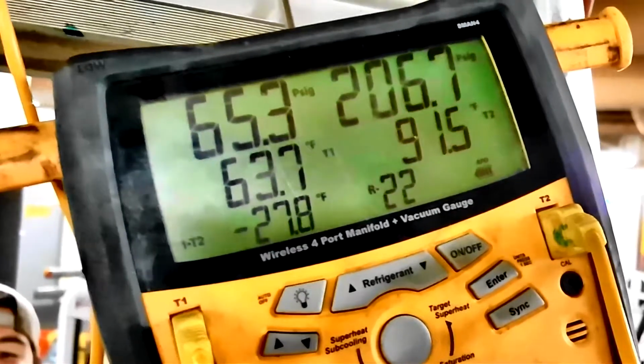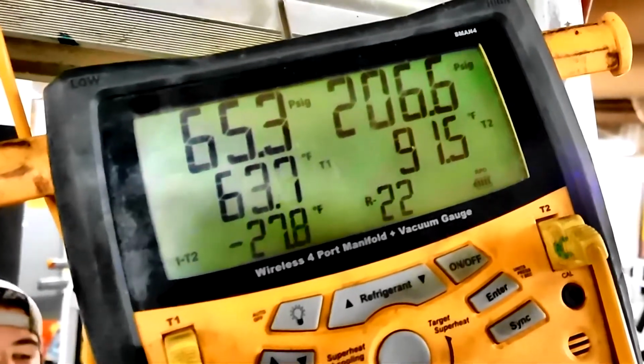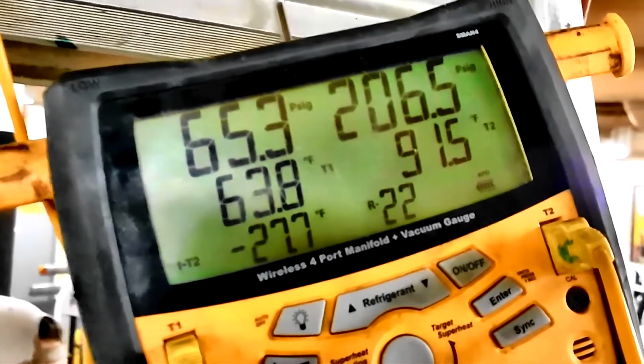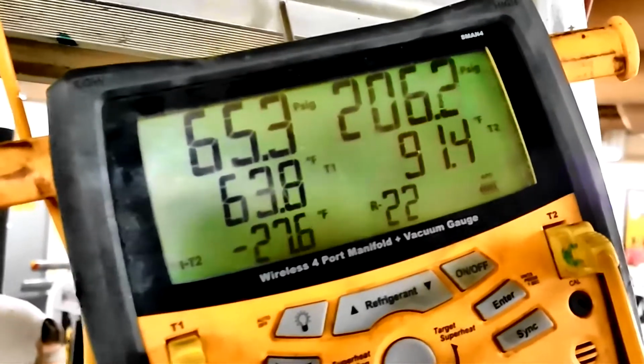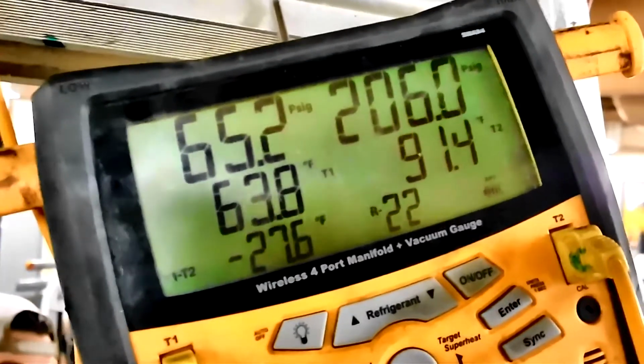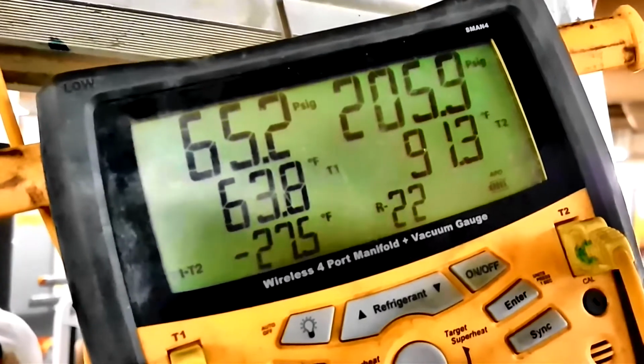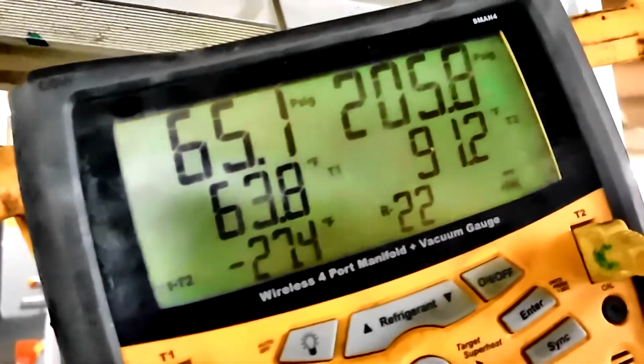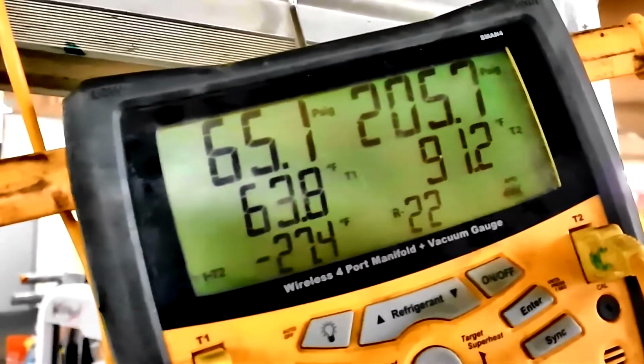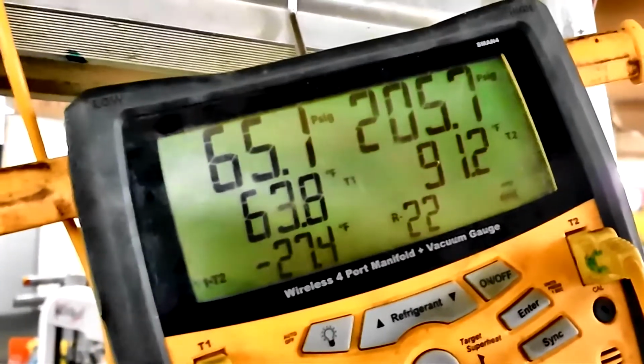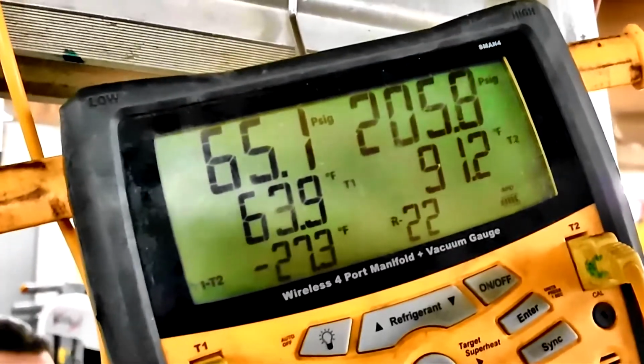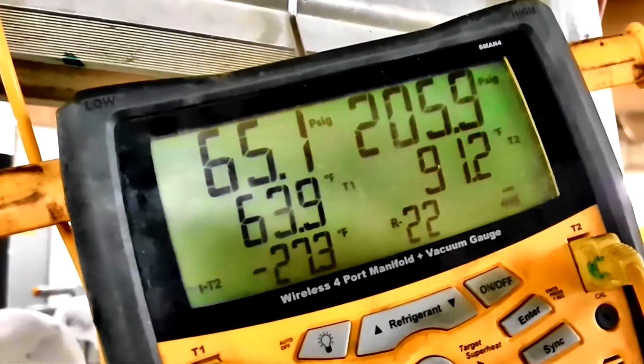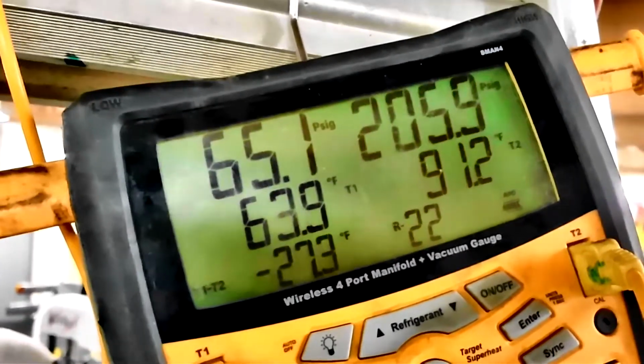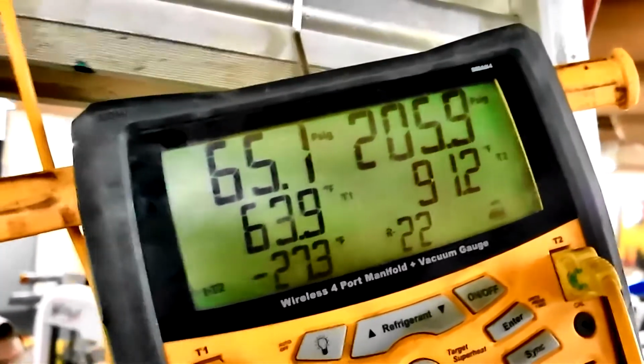The strainer is back in place. The unit is back online. So the head pressure went from 360 psi to 206 psi. The suction pressure went from 80 psi to 65.1 psi. As you can see, the thermocouple is still on my return water. The temperature of the return water is 91.2 degrees. Once again, the water coming into the unit is 80 degrees. So right now at this point we have 11.2 degree split.